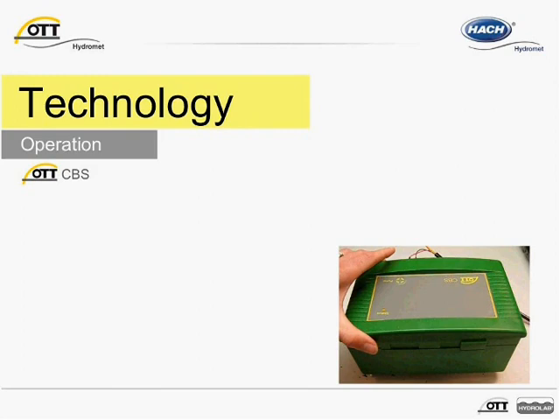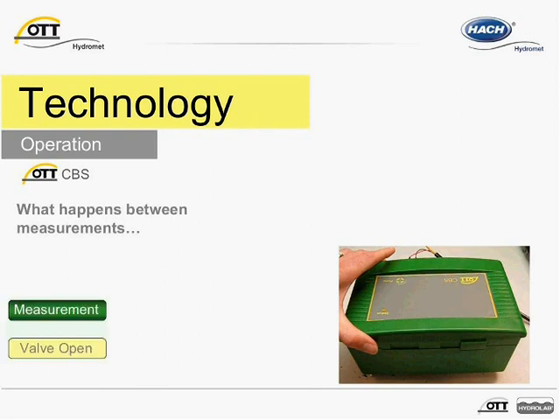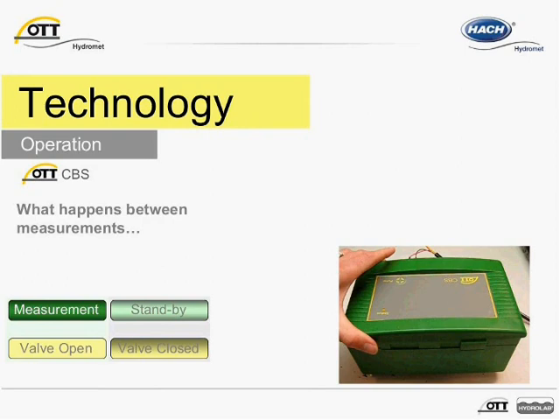One might ask: how does the unit maintain pressure in the measuring tube between measurements? The CBS is equipped with a differential pressure valve that opens and closes the entrance to either the measuring tube or vent for atmospheric pressure. When the CBS is not measuring, the valve closes off the entrance to the measuring tube. Also keep in mind that the bubble chamber attached to the end of the measuring tube in the water acts as a buffer. We'll take a more in-depth look at the bubble chamber in a few minutes.